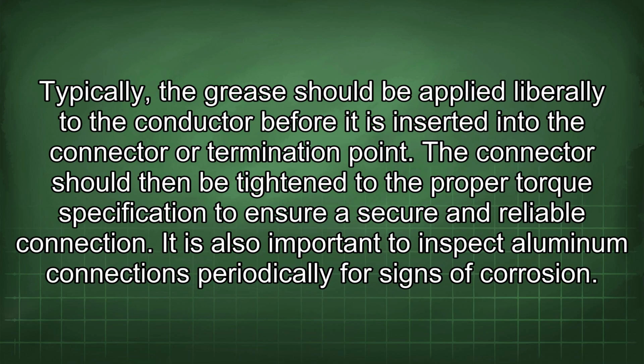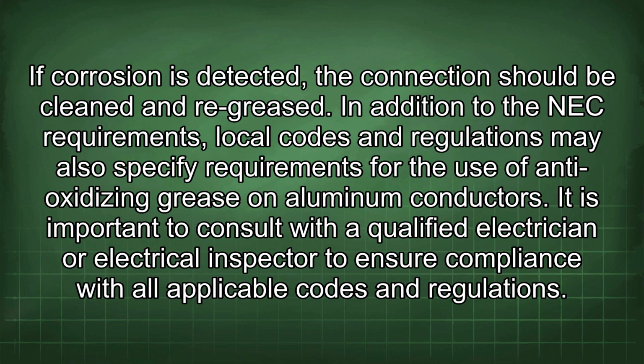When installing aluminum service entrance conductors, it is essential to follow the manufacturer's instructions for applying anti-oxidizing grease. Typically, the grease should be applied liberally to the conductor before it is inserted into the connector or termination point. The connector should then be tightened to the proper torque specification to ensure a secure and reliable connection. It is also important to inspect aluminum connections periodically for signs of corrosion. If corrosion is detected, the connection should be cleaned and re-greased. In addition to the NEC requirements, local codes and regulations may also specify requirements for the use of anti-oxidizing grease on aluminum conductors. It is important to consult with a qualified electrician or electrical inspector to ensure compliance with all applicable codes and regulations.